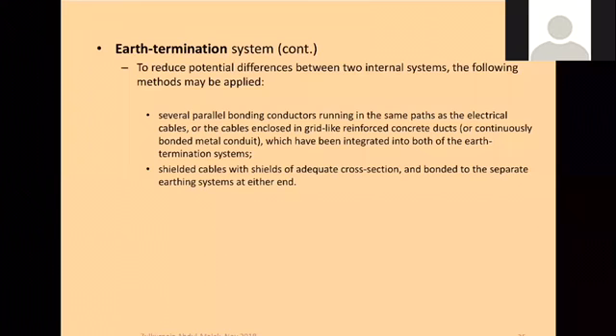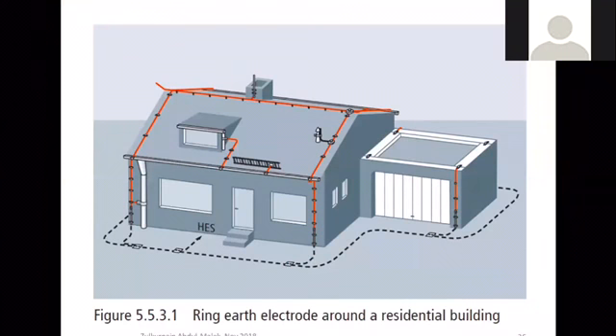We described paralleling the down conductors and so on, to reduce the potential difference by making the current flow in many ways. To reduce the potential between two internal systems, the following methods may be applied: bonding, as well as shielded cables and shield cross sections, as you can see here. So this is the earth termination, type B, because it's a loop that is buried, and the down conductors are shown there.